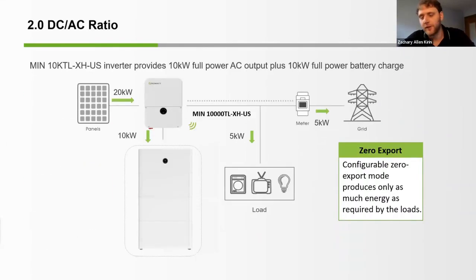As we discussed earlier, the MIN has a 2.0 DC to AC ratio. So a 10 kilowatt inverter can accept a 20 kilowatt array to maximize the usage of space on the roof. So while PV production is at 20 kilowatts, the 10 kilowatt inverter is able to output its full power to the load center of the home and also charge the battery with an additional 10 kilowatts of power. This is really exceptional, as your customers can charge the battery, be self-consuming, and sell energy back to the grid all at the same time.